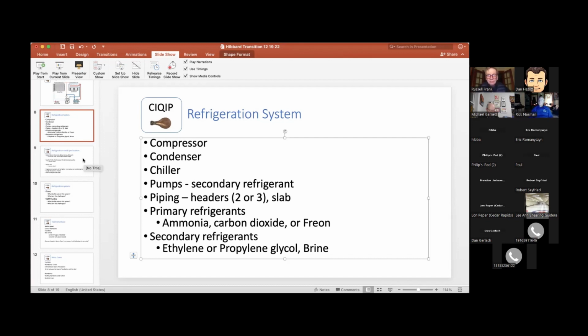The more tubes you have and the longer your header, in order to get a balanced flow through the floor, you feed it from the entry side and return from the far side. This way you have equal pressure at every tube—the first one in is the last one out, the last one in is the first one out. So everything is balanced and they do a great job. Almost all big rinks, like hockey rinks and big curling clubs, use reverse return headers.